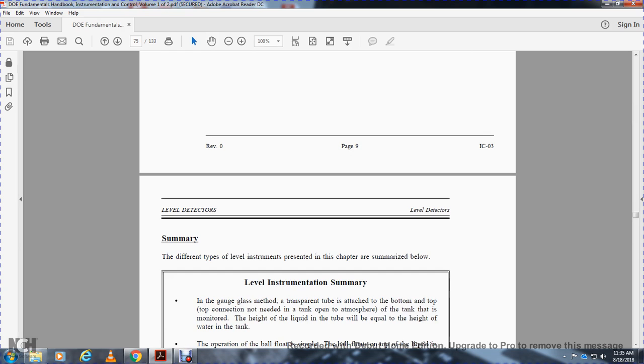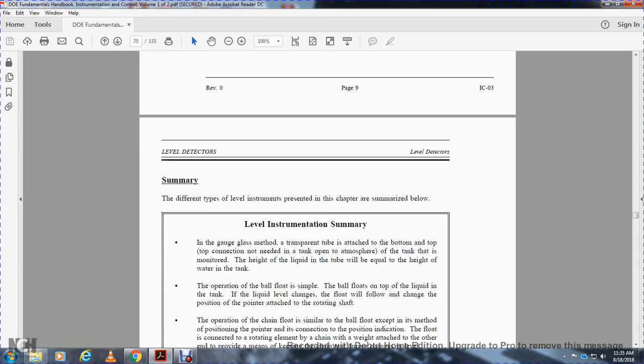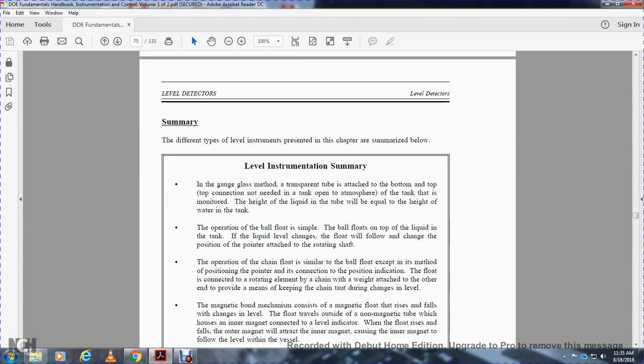Summary: the different types of level instruments presented in this chapter are summarized below. Level instrument summary. The gauge glass method uses a transparent tube connected at the top and bottom of the tank. The top connection is not needed if the tank is open to the atmosphere. The height of the liquid in the tube will be equal to the height of the liquid in the tank.